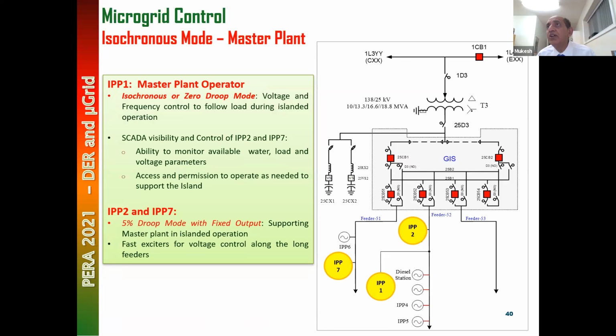The reactor, we saw inverter mode. We talk of grid following and grid forming. These are the new terms, sexy terms used by electronics engineers. What did we do in the old days? We didn't have grid forming and grid following modes. Actually, we had a different name. The IPP1 in a microgrid mode operates in what is called isochronous or zero droop mode. That means it is like an infinite inertia machine. The frequency and the voltage control is fixed when it is operating in a microgrid mode. And the regulation, the load going up and down, is helped by the droop from machines 2 and 7. So 1 is supplying a fixed base load, controlling the frequency and voltage like a utility system. 2 and 7 are providing a droop and voltage control depending on regulation.